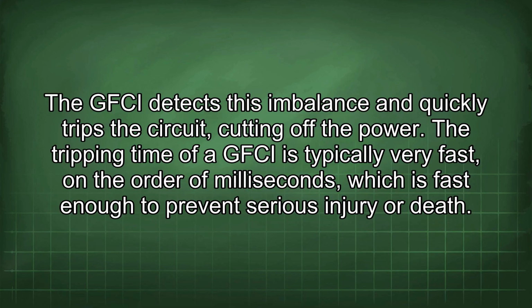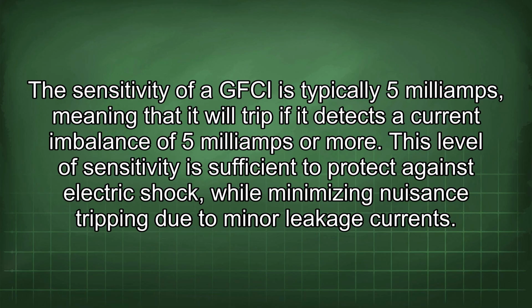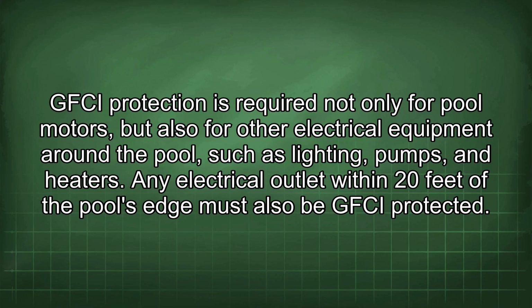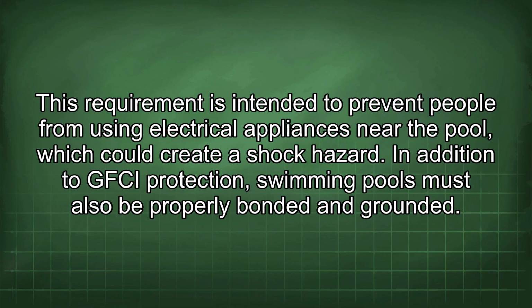The tripping time of a GFCI is typically very fast, on the order of milliseconds, which is fast enough to prevent serious injury or death. The sensitivity of a GFCI is typically 5 milliamps, meaning that it will trip if it detects a current imbalance of 5 milliamps or more. This level of sensitivity is sufficient to protect against electric shock, while minimizing nuisance tripping due to minor leakage currents. GFCI protection is required not only for pool motors but also for other electrical equipment around the pool, such as lighting, pumps, and heaters. Any electrical outlet within 20 feet of the pool's edge must also be GFCI protected. This requirement is intended to prevent people from using electrical appliances near the pool, which could create a shock hazard.